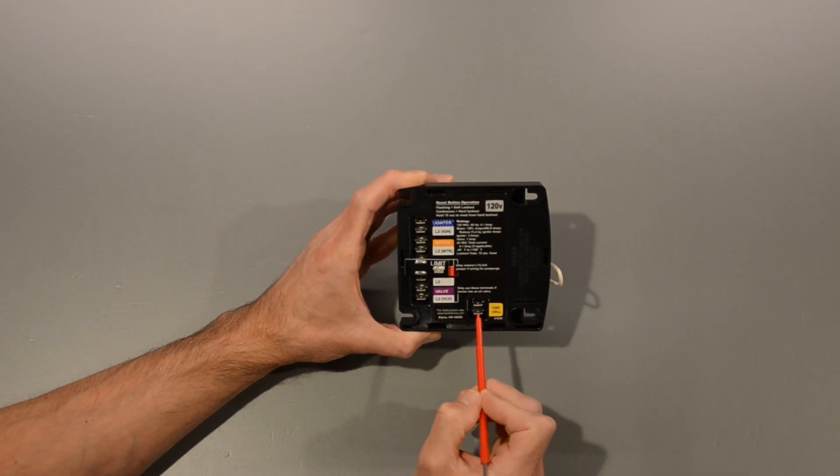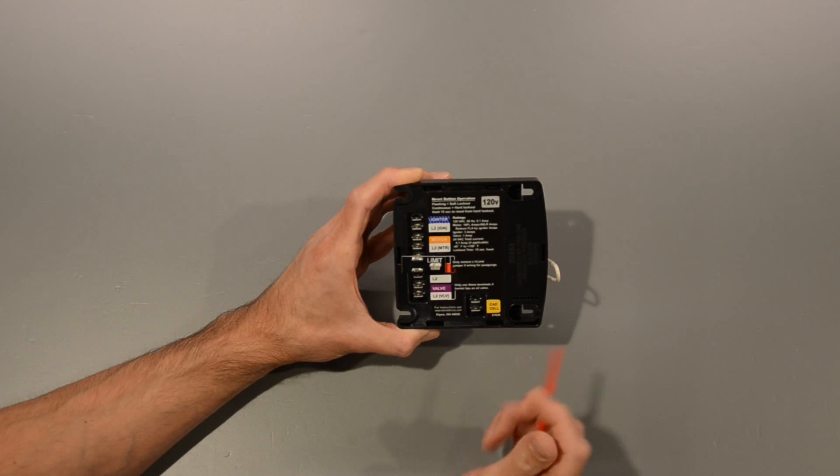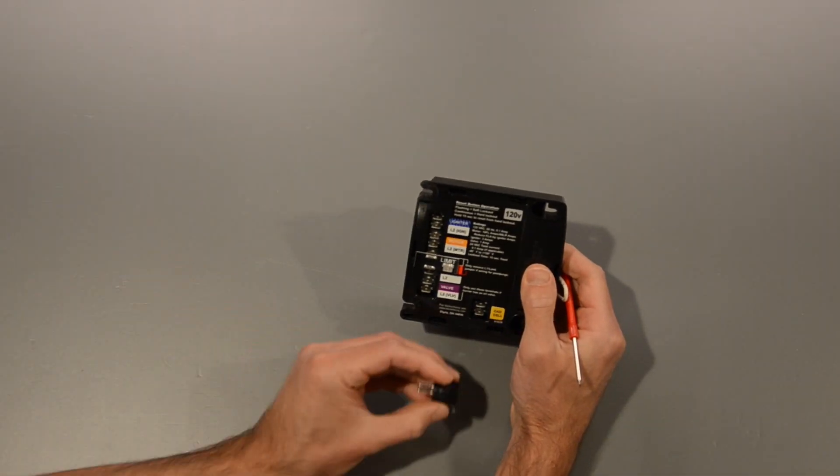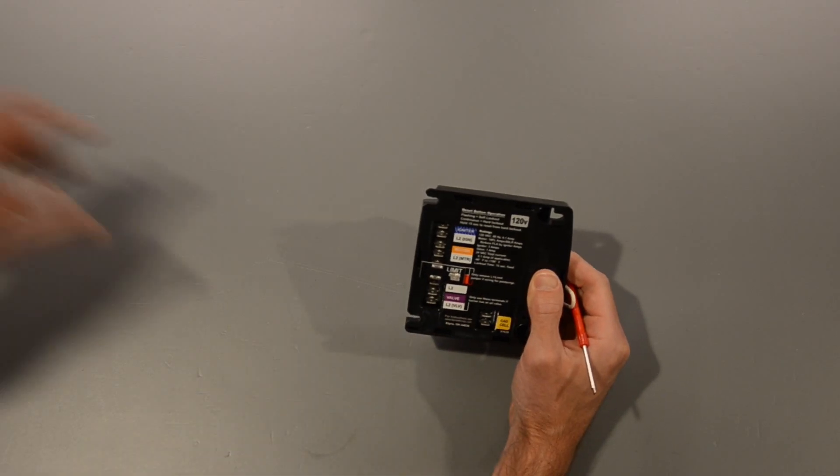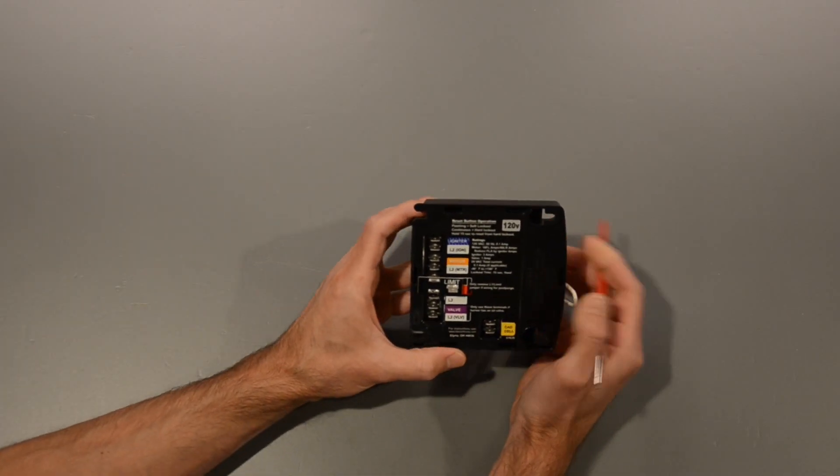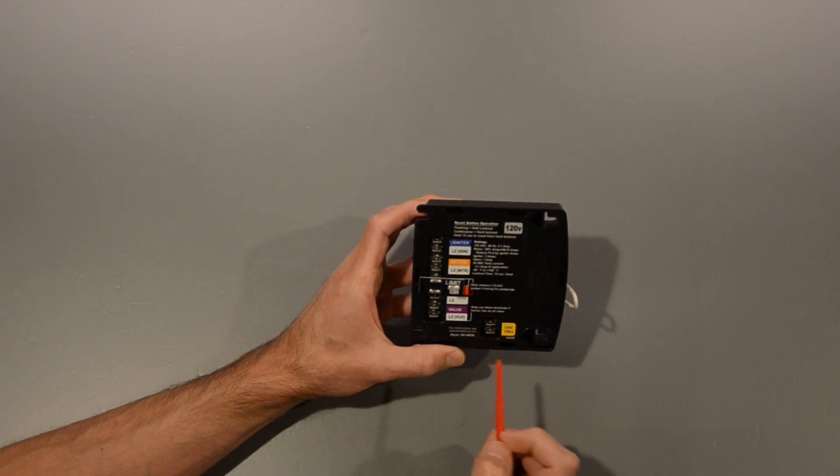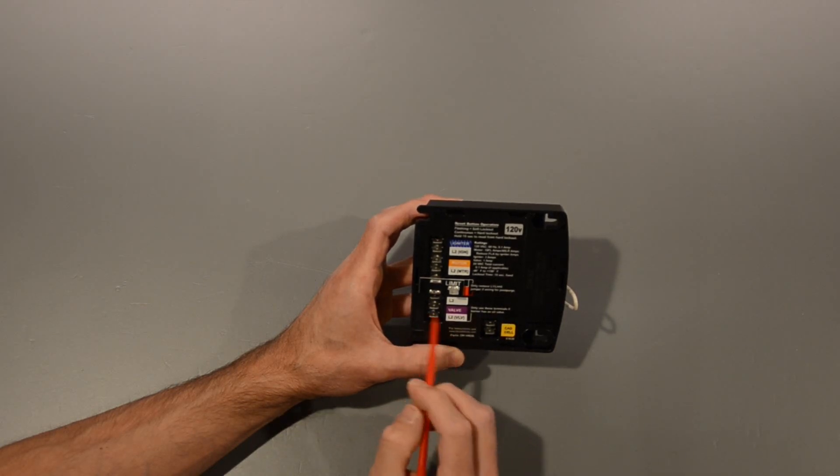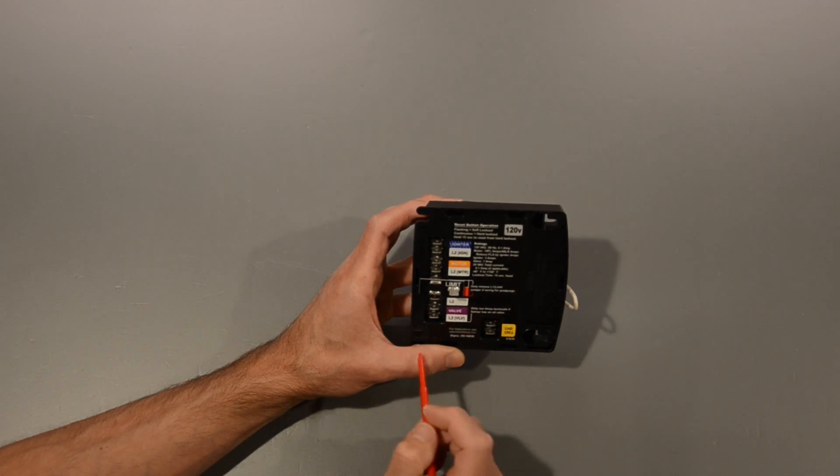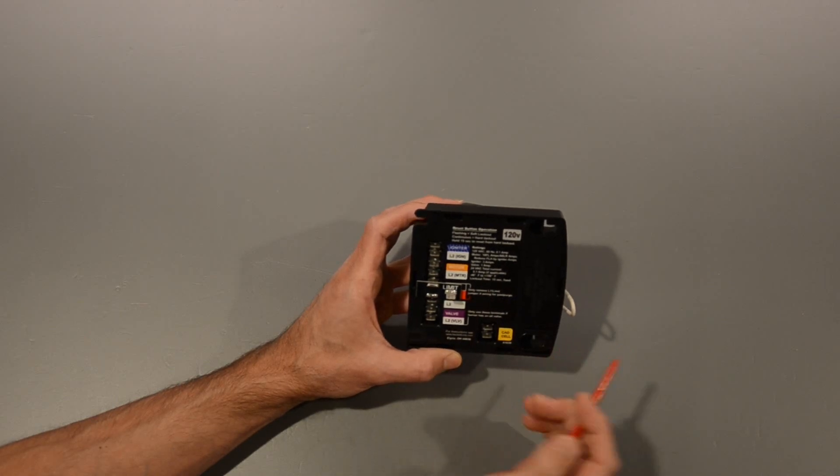There's also a cadmium sulfide cell that connects to these terminals, and that acts as a safety feature. This is what it looks like, and this acts as a flame detector. After that 15 second period, as long as this cadmium sulfide cell is not detecting light, meaning there is no flame, it will go ahead and open the solenoid valve to allow the system to ignite. If this does detect light before that time period, this will trip out on safety and shut everything down.